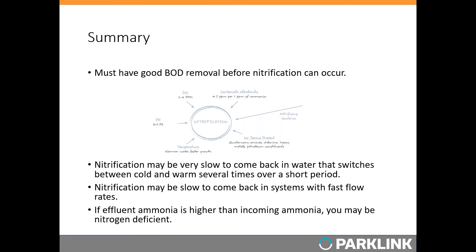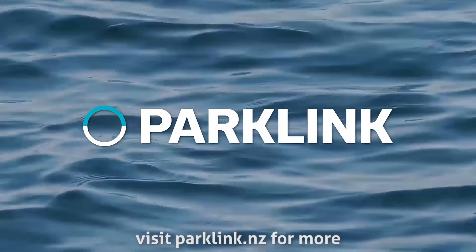Common signs of nitrogen deficiency include effluent ammonia higher than influent ammonia, the presence of bulky filaments such as Type 021N or Thiothrix causing bulking or high 30-minute settling, or sliming and high TSS from small, low-density flocs.